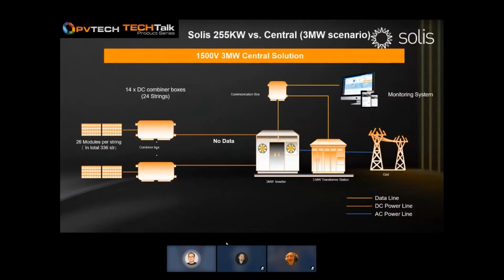First, I would like to share with you some scenario. We are working with a 3 megawatt central solution here. If you look at the chart, this is a 3 megawatt central solution. We'll be able to see what typically is 26 modules per string, 14 DC combiner boxes. If you could follow my laser pointer, 14 DC combiner boxes, which I assume your DC combiner box will have a standard 24 strings input.